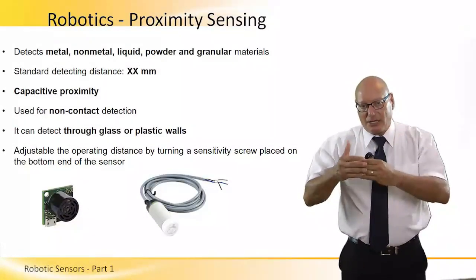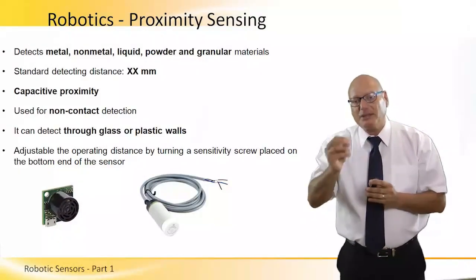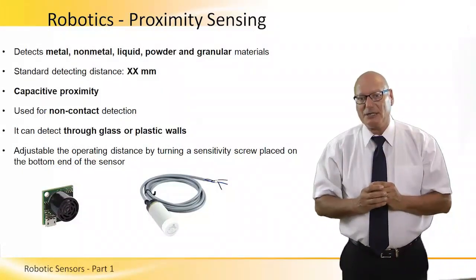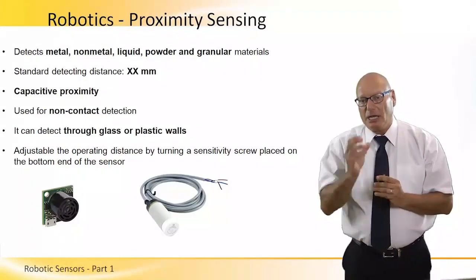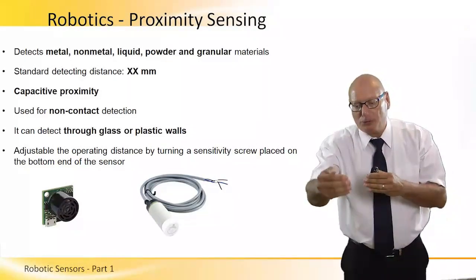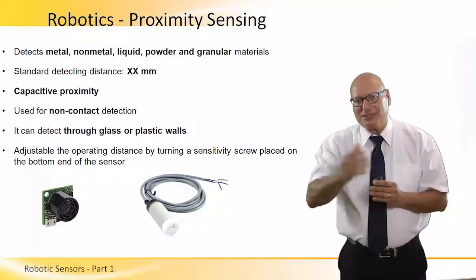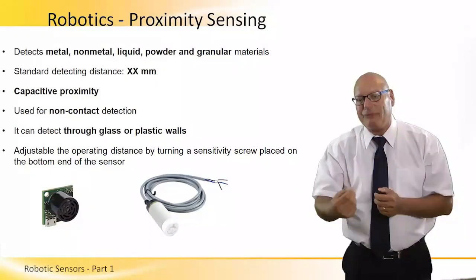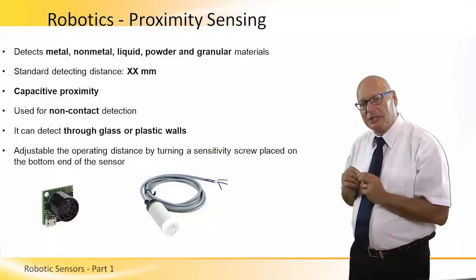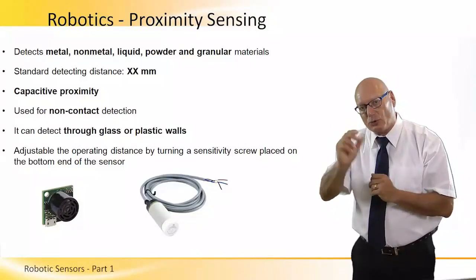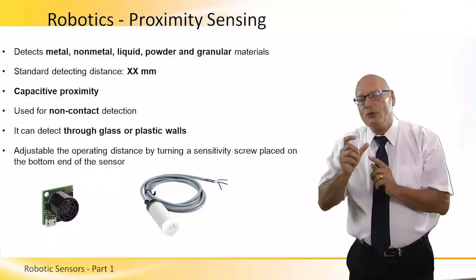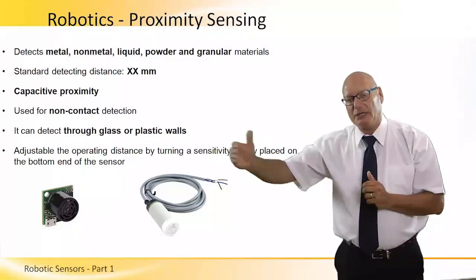Proximity sensing is a distance measurement that can detect metal, non-metal, liquid, powder, and granular materials. It is a capacitive type of sensing with no need for contact — even without touching, we can analyze the distance between the sensor and the object being sensed. The standard detecting distance can be varied according to the sensitivity level of the sensor, and in some sensors the sensitivity can be adjusted via a screw on the back to make it more or less sensitive. It is a non-contact range detector for a wide variety of materials.